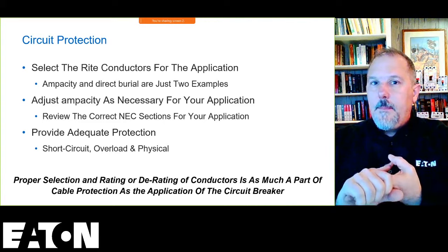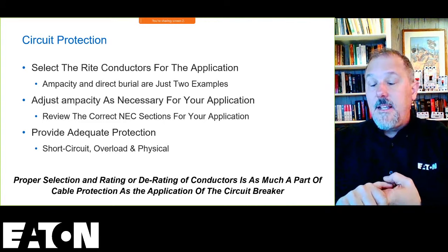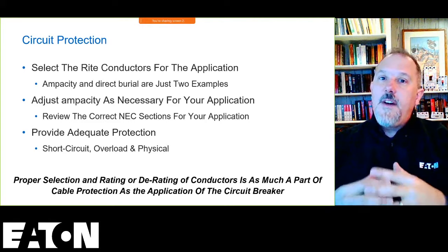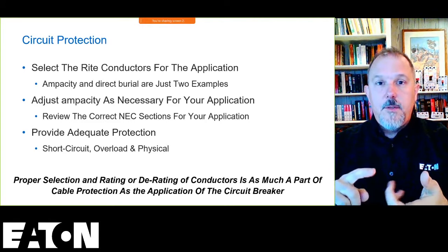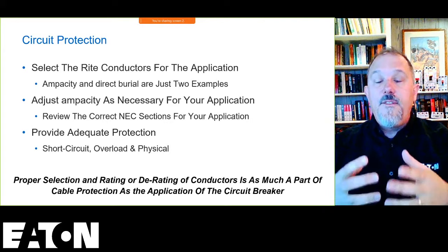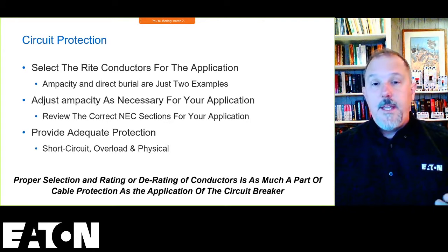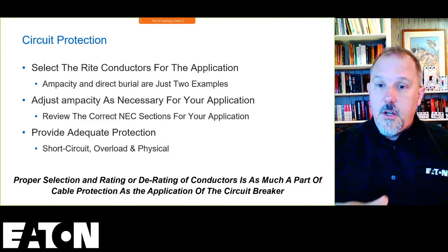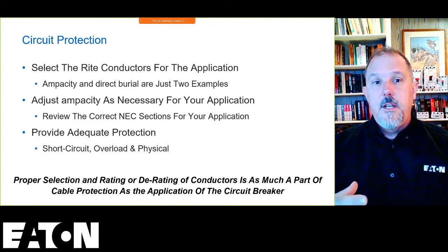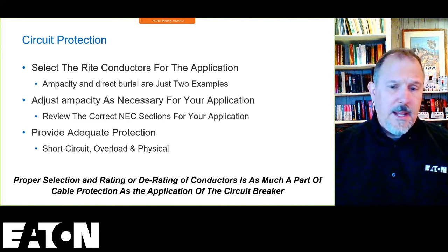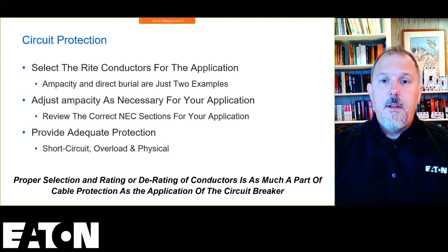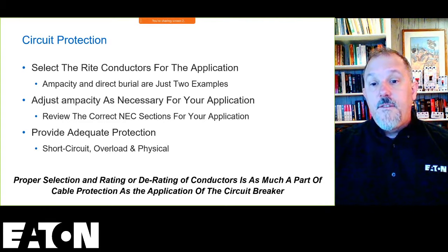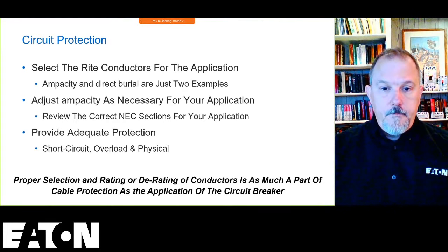You calculate the ampacity of the conductor correctly based upon its conditions of use, and then provide adequate protection, both from short circuit and overload, and I put physical protection in there as well, because we have to consider the proper physical protection. There are a lot of code requirements and sections. I'm probably not going to hit them all, but there are a lot of areas in the NEC that speak to protection of a conductor from a physical perspective as well.